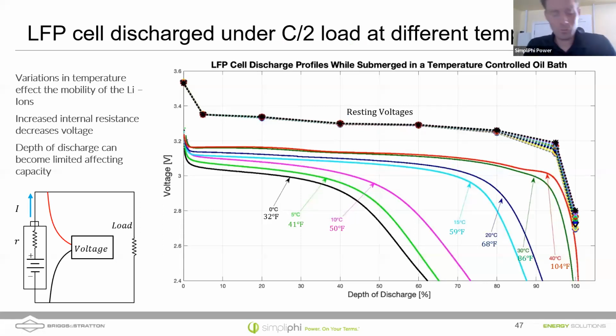Absolutely. So what you'll see in a battery cycle is that the cells themselves, the lithium takes a while to kind of get into its best resting place, if I can say it that colloquially. So when you discharge a battery, let's suppose you discharge down to a cutoff of 48 volts, but you're in a discharge cycle to get there, right? You might hit 48 volts, and then as soon as your low battery cutout kicks in and you stop discharging your batteries, you'll see the battery cells rebound. And typically, they'll rebound to what that resting voltage equivalent would be.